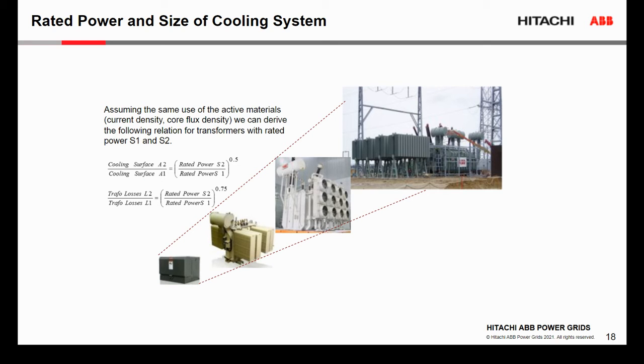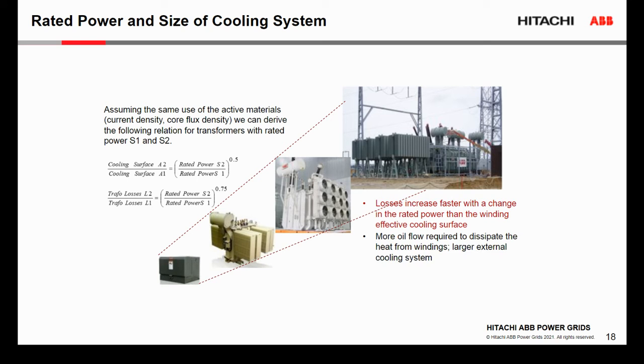The size of the cooling changes significantly with the rated power of the transformer. The losses increase much faster than the cooling surface of the transformer, and for larger units, the tank is not sufficient to dissipate all the heat. So we add the radiators, and we add the fans, then we add coolers, we add pumps, because we have much higher losses. We produce much higher losses in larger units, and we need a more efficient cooling system.